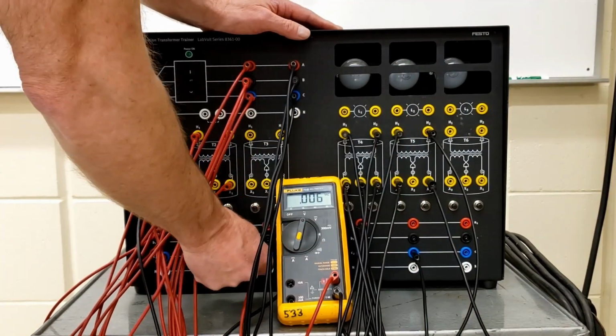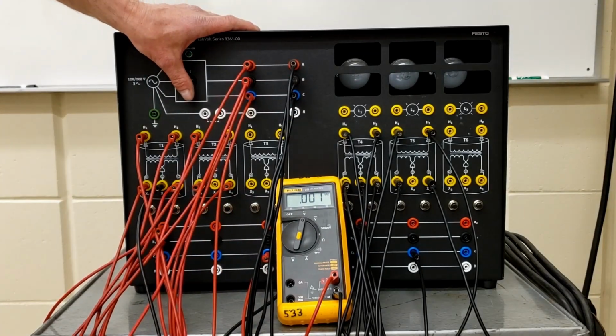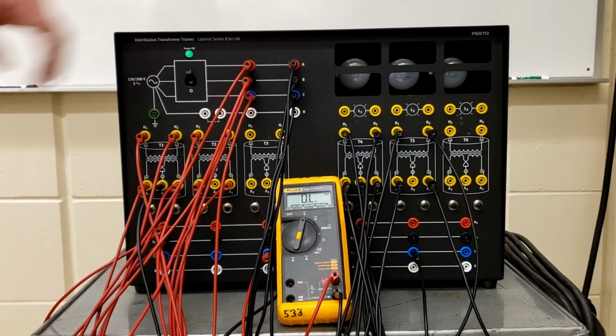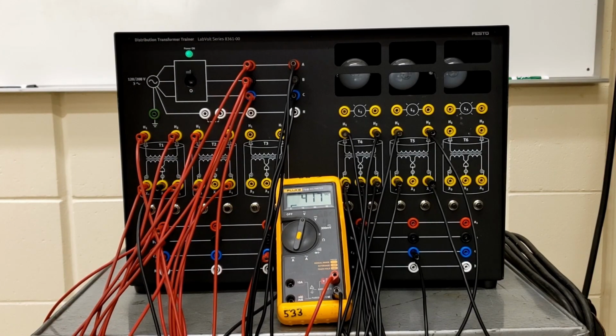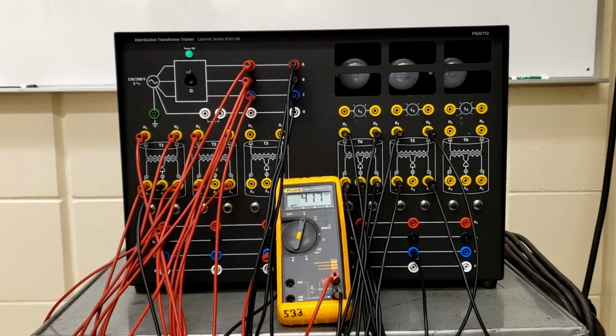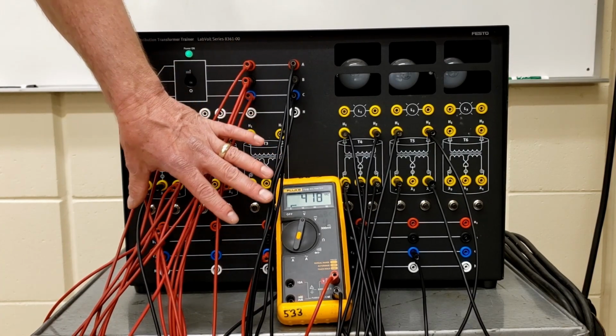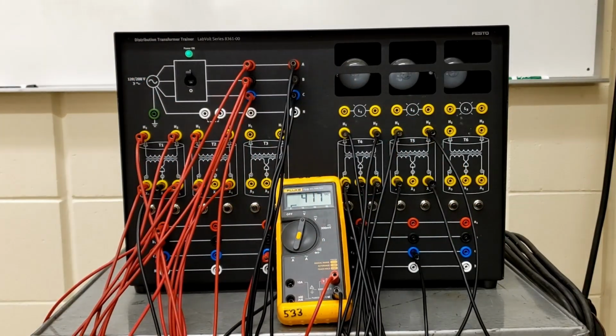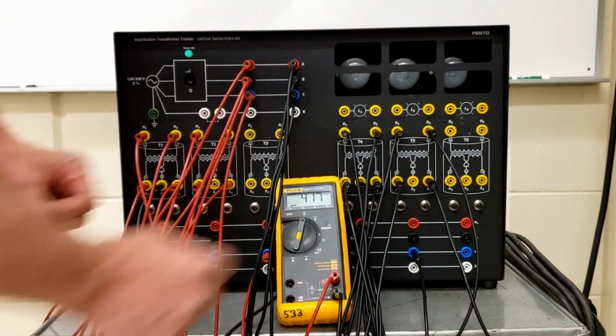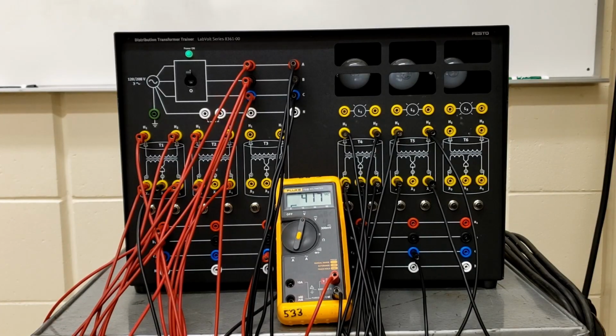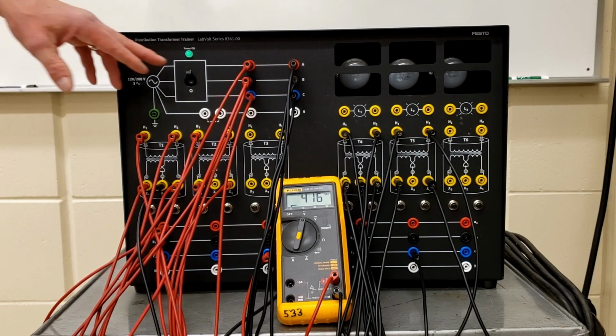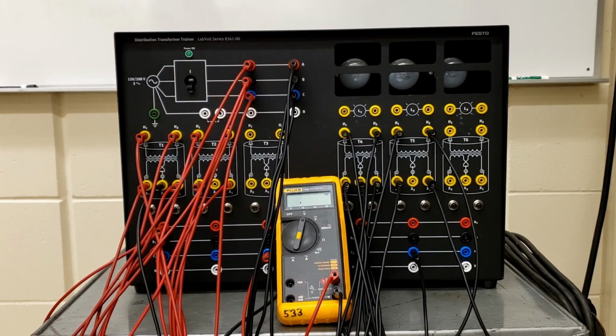Okay? And now let's see what we have between the C phases. This will be interesting because this is an open delta, it's not a closed delta, right? So let's see what that voltage is between the two C phases. Okay, so now we got the same voltage, we got 417 volts between the two C phases. So identical voltages to what we saw on the closed delta. So again, we have a 0 degrees phase shift here on the secondary. We have a 180 degree phase shift on the secondary of the second open delta. We had 240 between the two A phases, 240 between the two B phases, and now 416 volts between the two C phases. Identical to what we saw on the closed delta phase shift, voltage differences between the phases.